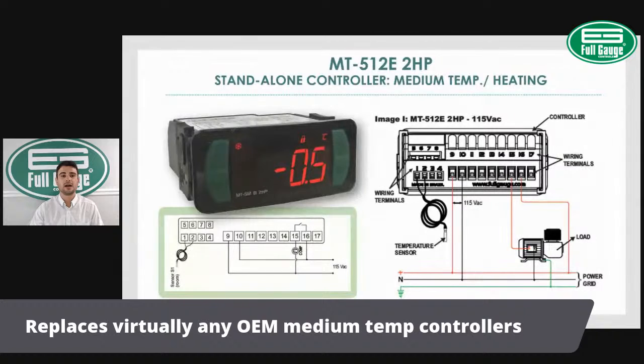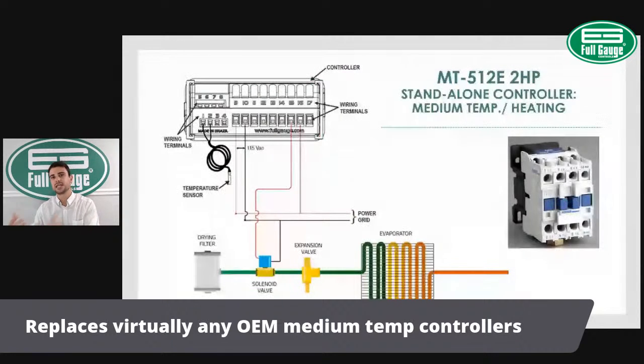So now let's say we don't want to control the compressor directly. Let's say we want to control the expansion valve, the solenoid valve in that case. We have the controller powered up in 110. Again, we have neutral going into terminal 10 and the hot line going into terminal 9. And that terminal 9 is also feeding power to my relay circuit on terminal 16. Once the relay closes, power comes back from terminal 15 and feeds my solenoid valve, which will be activated or deactivated. So that's how you wire this 512 in 110 volts.